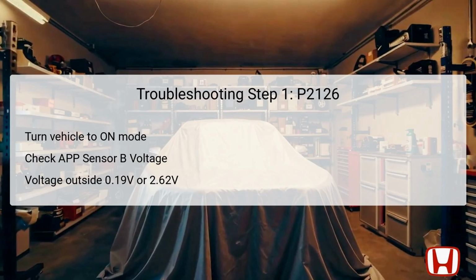A reading falling below 0.19 volts or exceeding 2.62 volts confirms the presence of a fault. This diagnostic step helps to replicate the condition under which the warning code was triggered. In case of such deviations, further investigations into the APP sensor and its connections will be required. This initial check is foundational, as it primes the technician for more in-depth diagnostics and repairs.